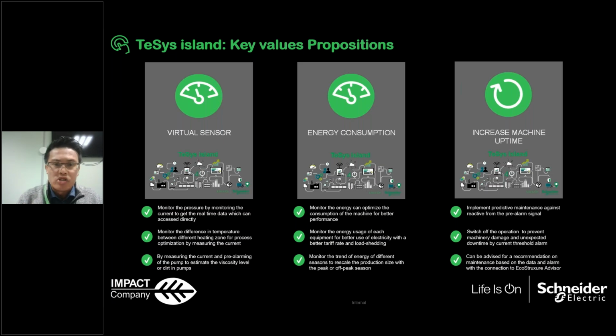So the energy consumption is very important, or very critical to the customers, especially for this energy crisis. The third is to increase the machine uptimes. In other words, it is to reduce the unexpected downtime. How can we achieve this? Because in the TeSys island, in the system, we can set different thresholds, and then we can send out the alarm or the alert to the operator that something is happening.